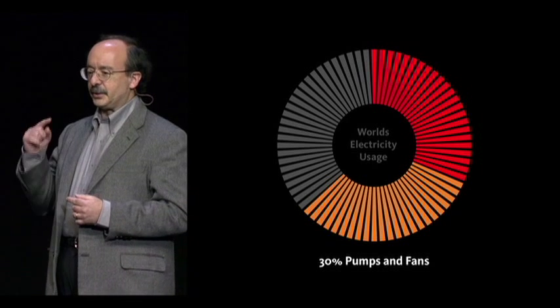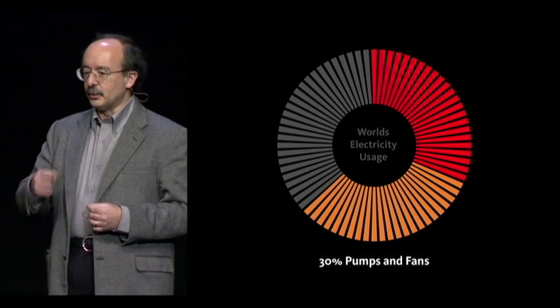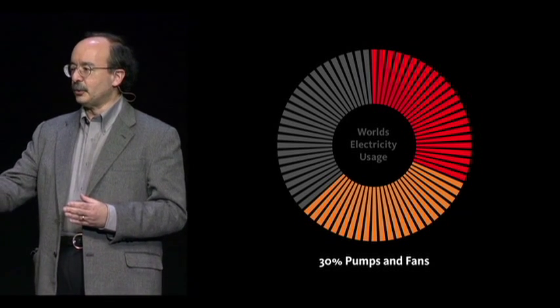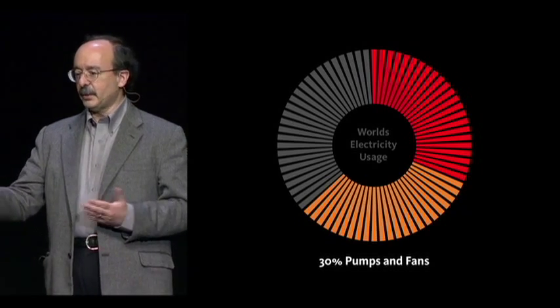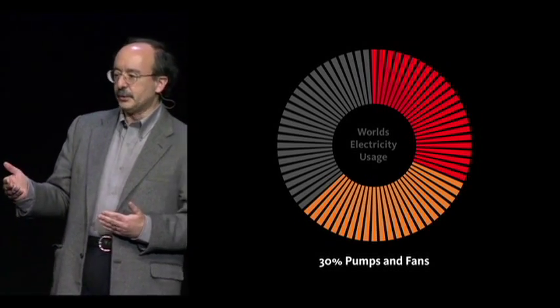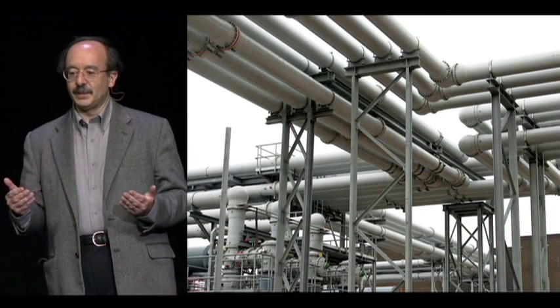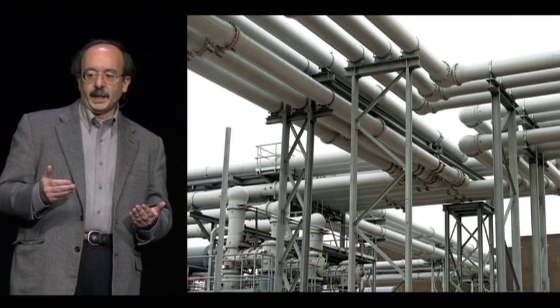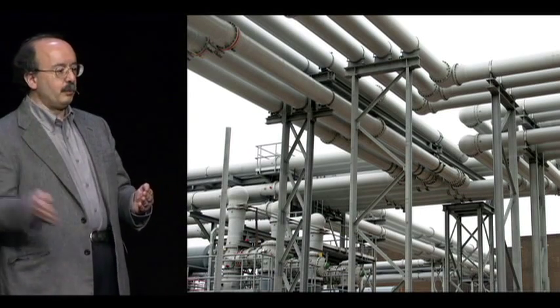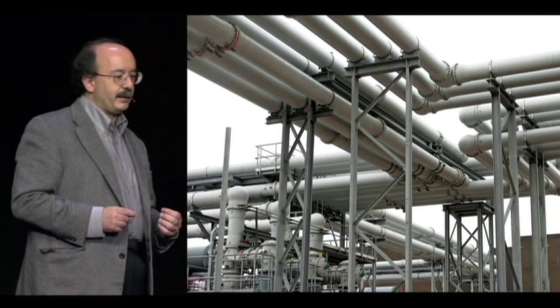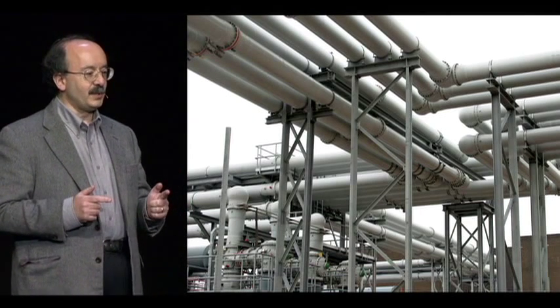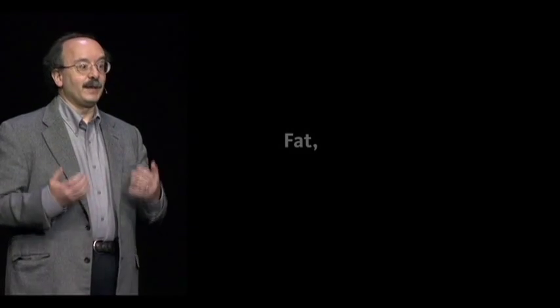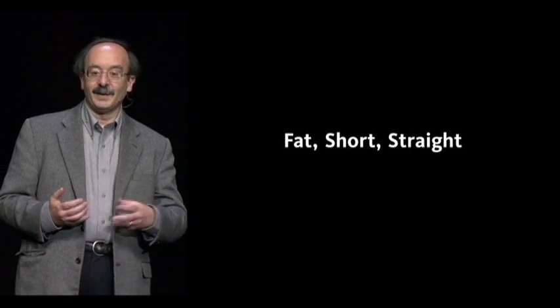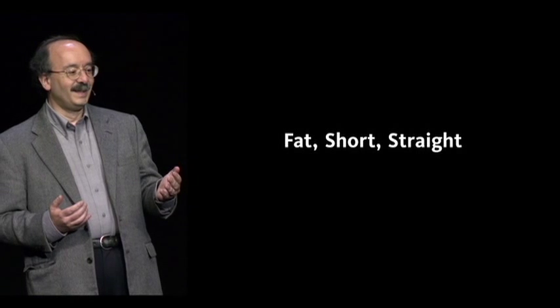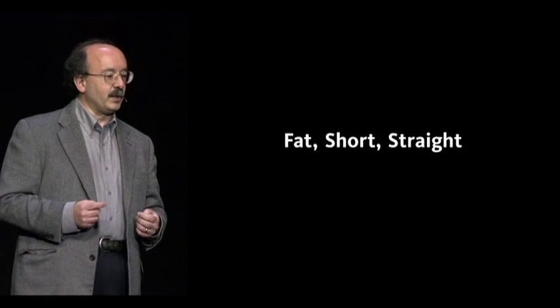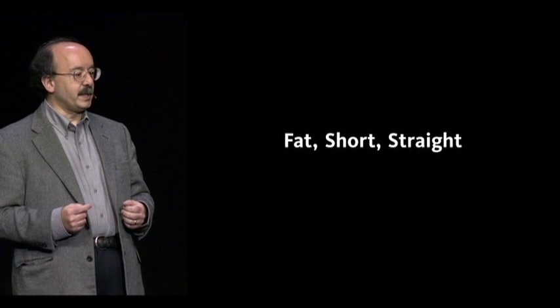But first, we should stop wasting most of the energy used by the pumps, fans, and other motor-driven devices. For example, pumps, the biggest use of motors, move fluid through pipes. Redesigning one typical industrial pumping loop cut its pumping power by about tenfold at lower capex just by using fat, short, straight pipes instead of thin, long, crooked pipes. And the designer who did that probably left another fourfold or so savings on the table.